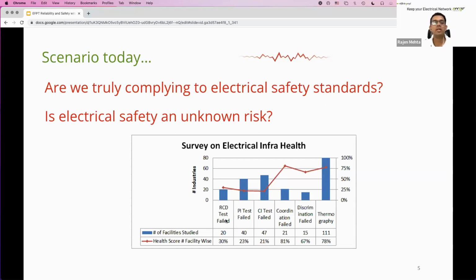First, for example, the residual current device test — a simple test for checking the health of the earthing device provided in a premise, where present. Even in cases where they are present, we've found that 30% of these RCDs are not performing their true function. Either they trip too fast, causing nuisance tripping, or they don't trip at all, or they require excessive leakage current to act. So the whole purpose of the residual current device, or earth leakage circuit device, gets defeated.